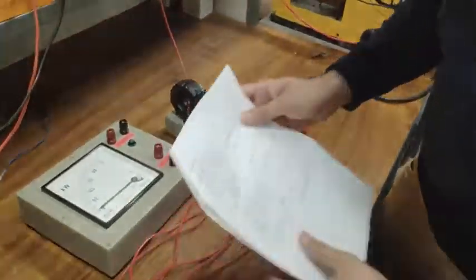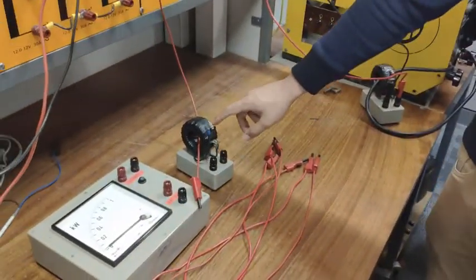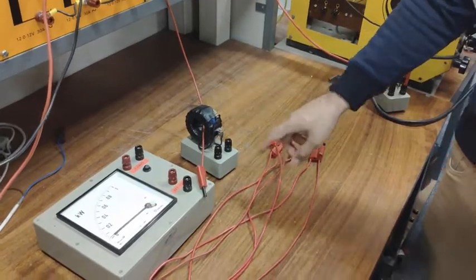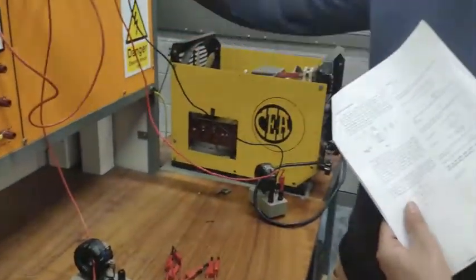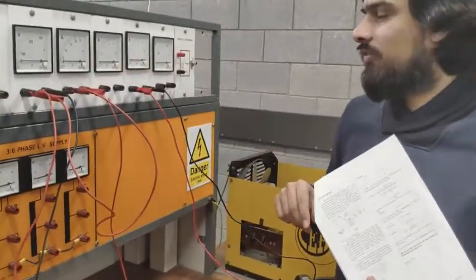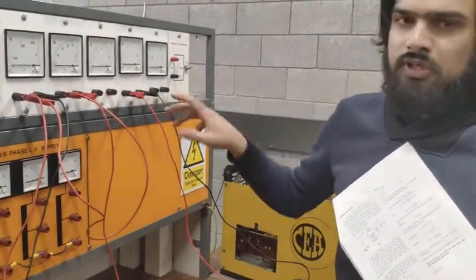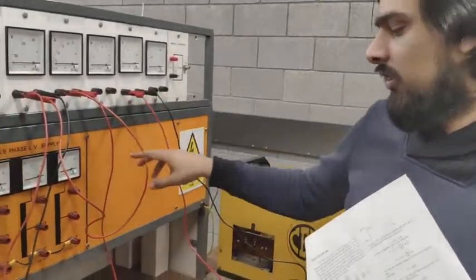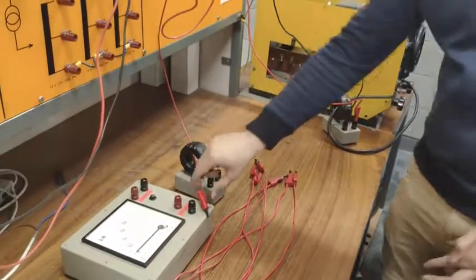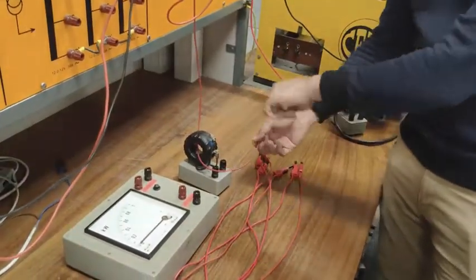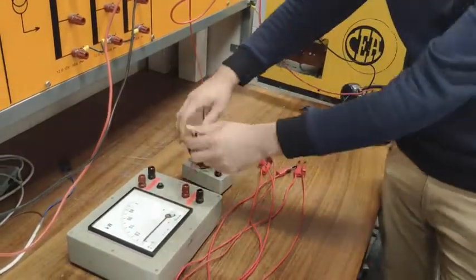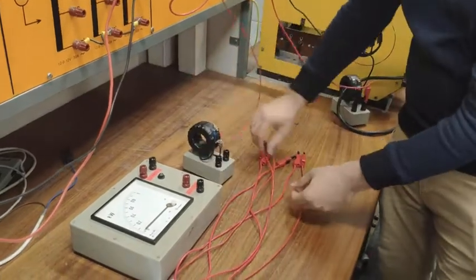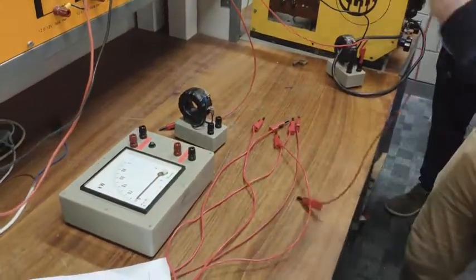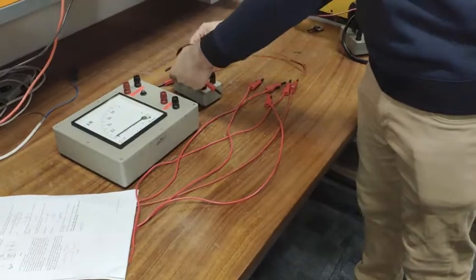Now, as we know that the turn ratio of the CT is 120 to 5, and from the rating of the transformer, the rated current of the transformer will be around 20 amps. So it's a very low current. So we need to fix some turns around the CT so we can increase the sensitivity. So I will make 4 turns.